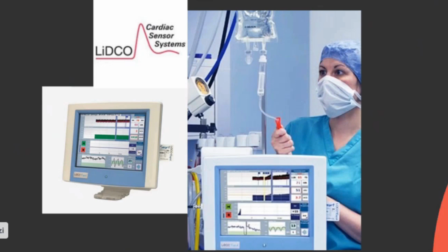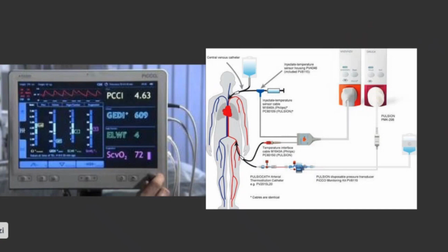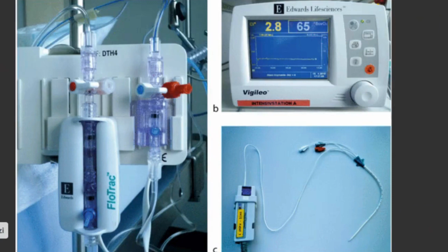The next one is called the PiCCO. I don't know if anyone has come across it. It uses thermodilution. You take an ice bucket with ice cold water, and then inject it into the central line, and it measures how quickly the temperature changes, I think it's 4 degrees that we normally have. The fluid is usually sitting in the ice bucket, and it measures the change in temperature from when you inject it until it gets to the A line. So again, it uses that as a calibration method, and then relies on the pulse contour to give you your dynamic measurements.